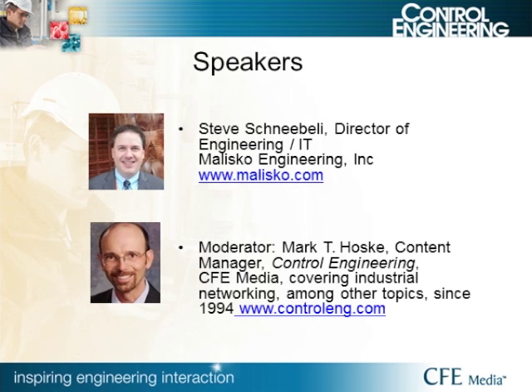Question: When you had that Motor Control Center, did shielding help when you rerouted? We didn't use shielding in that particular case, but we have in other installations and that's definitely what helped — shielding would be a key solution for that type of problem. Thanks, everybody, for the great questions. We'll try to get to unanswered questions offline. I'd like to close by thanking our great speaker, Steve Schneebeli, for generously sharing his time and expertise with us.